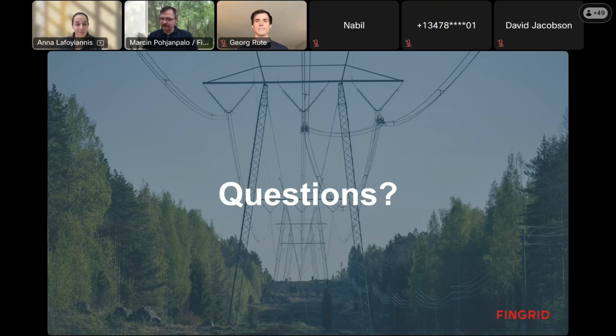The questions keep coming, which I'm so glad about. Vajik asks, how do you assess the maximum operating temperature per span when you run your DLR? And do you take into account the clearance standards versus the roads and ground, etc., so that the conductor does not sag too much?